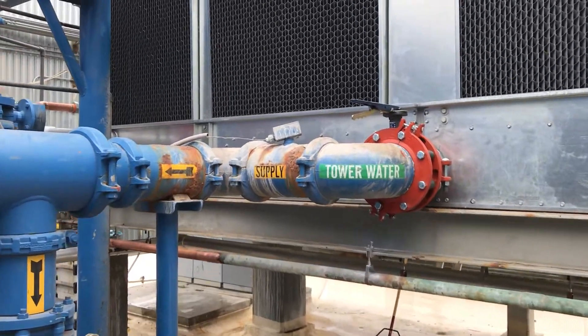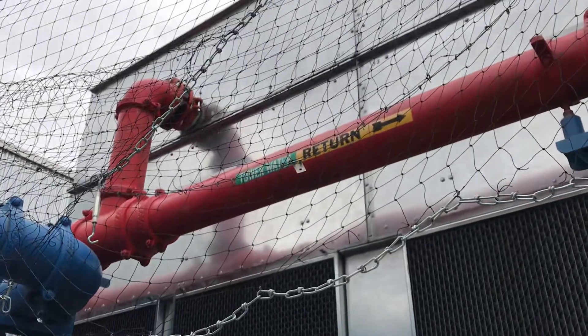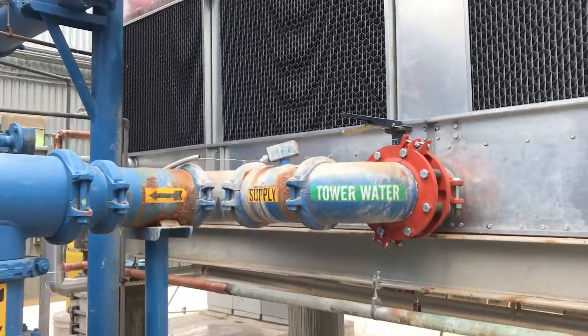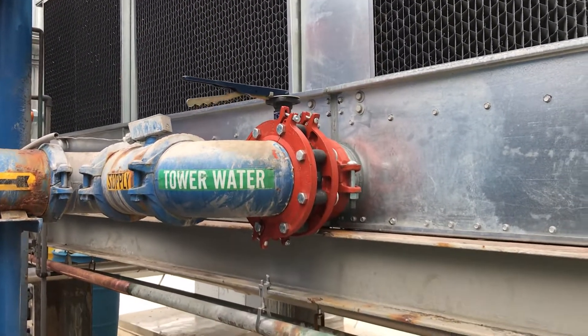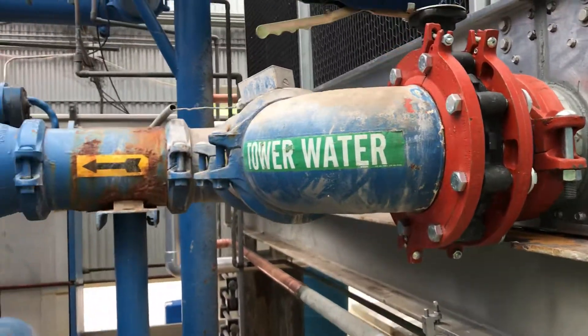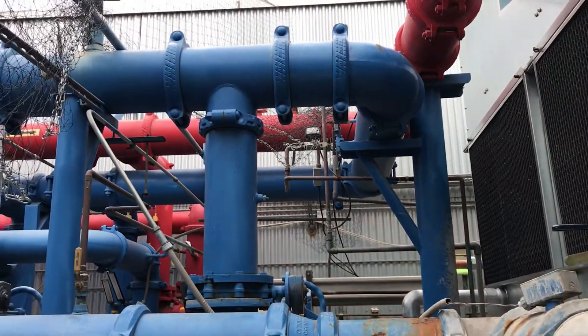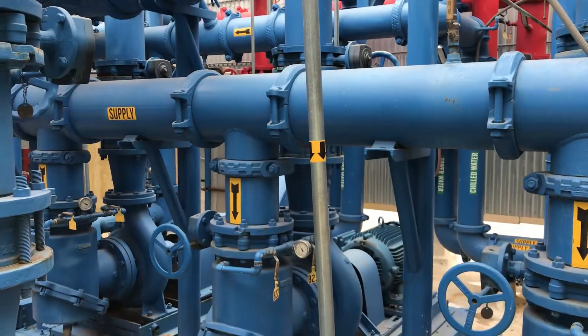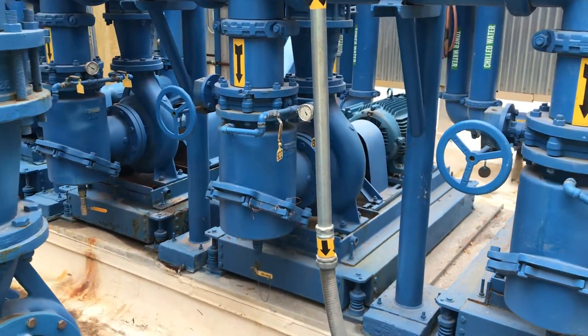There is a lot of rust on some of that piping. The customer did not want to replace it at this time — it would have actually been an optimum time to replace it, but they chose not to. You can see these valves; the butterfly valves are at an angle again. They'll have chains hooked up to them so they can access from below. Handles on the bottom valves — you can see all new butterflies, new Victaulic connections. We do not maintain this location; it is maintained by others, but it's actually in really, really good shape. The inside of the piping looked really great — a little bit of an eggshell, but no rust, no heavy rust inside the piping.